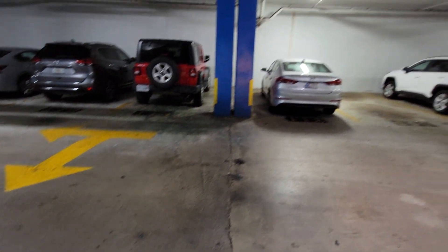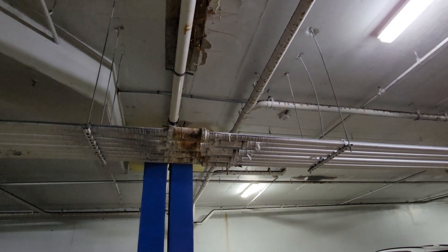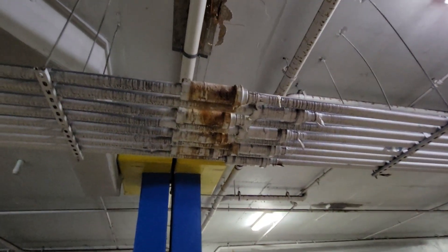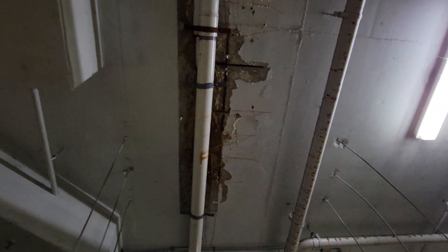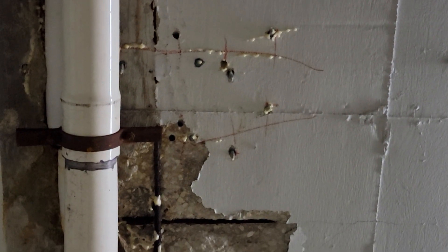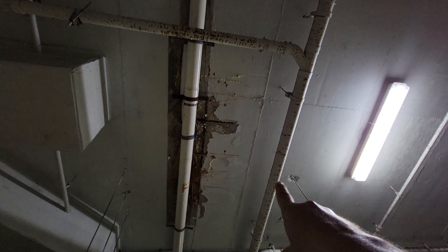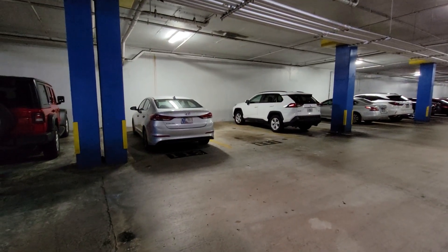Put a second set of experienced eyes on it. You can see the rusting on the pipes already from where it's been dripping on them. What happens when these finally rust through — and these might be sprinkler lines? As I look up, I think we're starting to see the beginnings of some stalactites up there. It's about 15 feet over my head so it's hard to zoom in, but you can see there's more there. It looks like somebody may have already been examining it and marking the lines, but I don't see any scaffolding or anyone working on it.